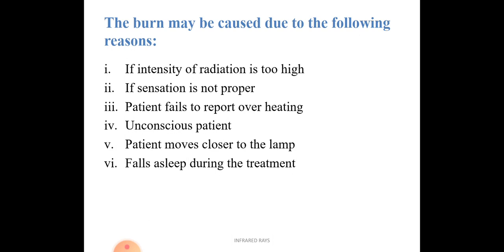Sometimes the patient moves closer to the lamp. So as per the inverse square law, we know that as the distance between a particular object and the source decreases, definitely the intensity will increase. Okay, so we all know the inverse square law. As the distance decreases, the intensity felt will increase, or the surface-area-wise intensity will increase. Many times the patient is sleeping during the treatment. So all these are factors that may be responsible for overheating of the part, and there are chances of burns.